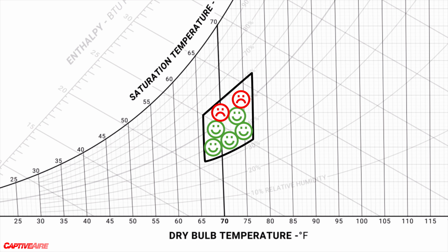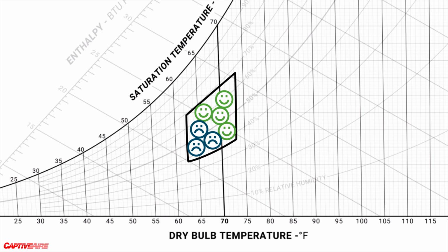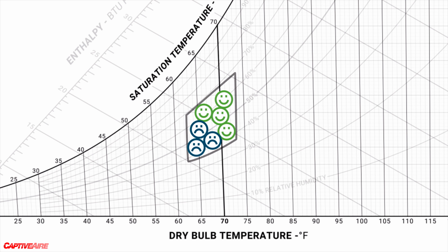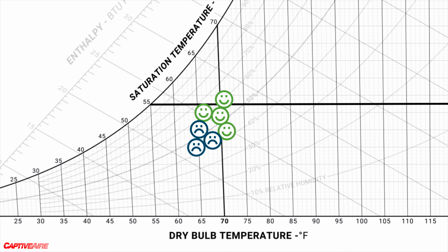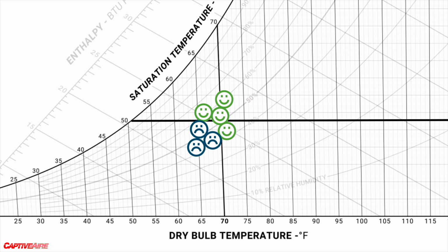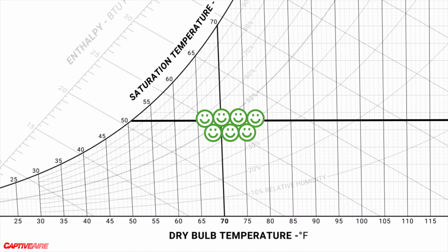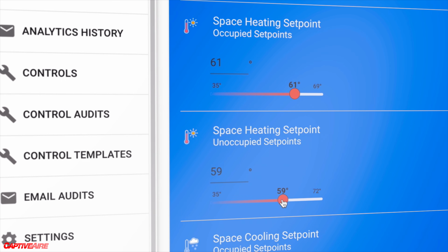So first we're saying, hey, can we go cooler and cooler in the summer? Is that going to help? But then some people are getting too cold. The best thing we found was actually dropping the dew point lower than what you'd typically be trying to shoot for on a space. A normal occupied space, people are often trying to shoot for around a 55 dew point. We started to find it's more like a 51, 52 degree dew point, sometimes even a little bit lower. It's higher energy use, but then you can have a wider variance of temperature before people start saying they're hot or cold if you start wringing the moisture out of the air a little bit sooner. So without CASLink, we'd have no idea where the best combinations fall.